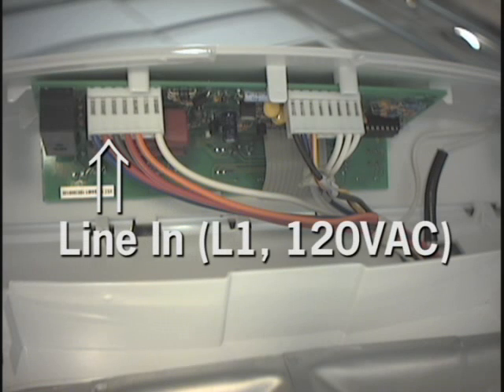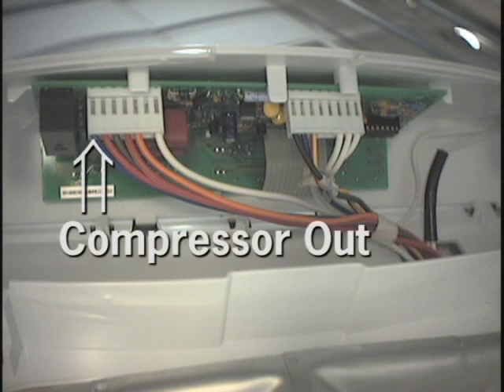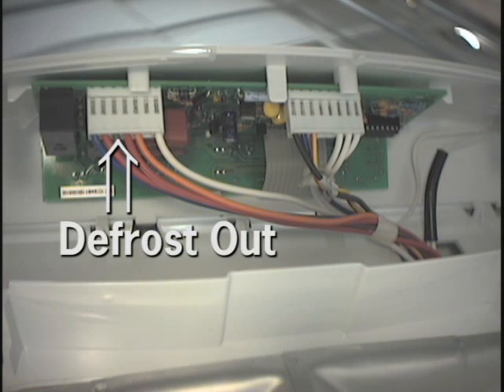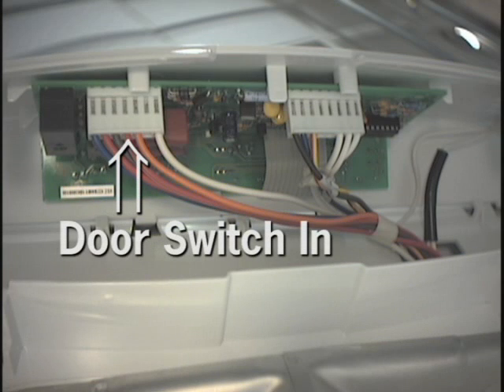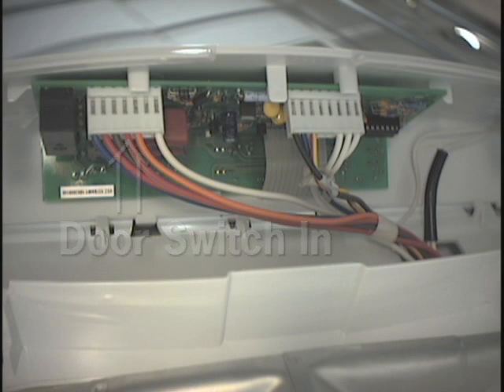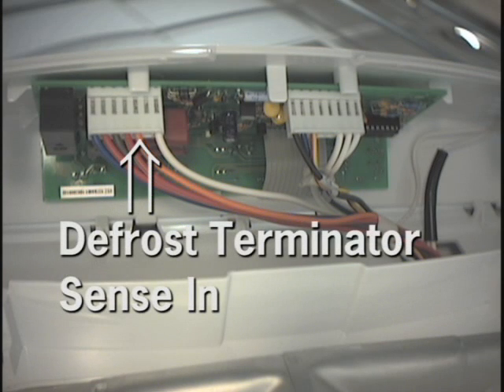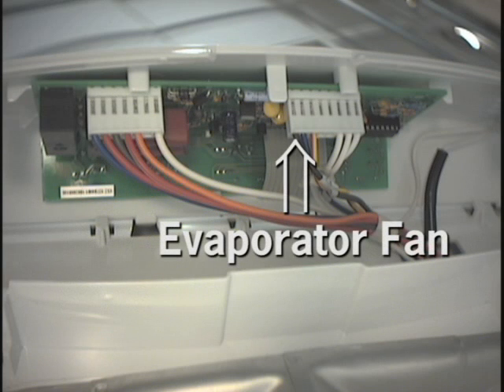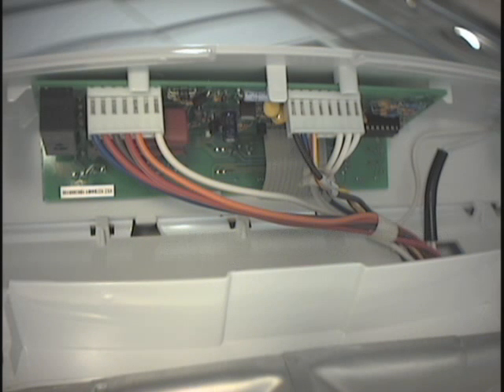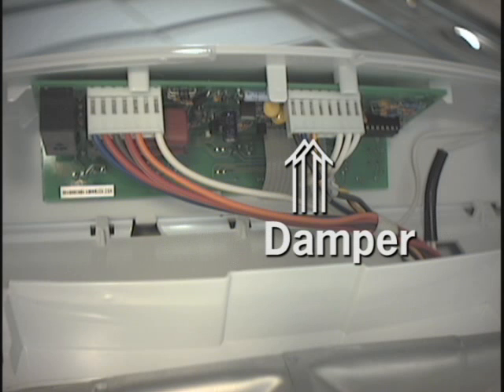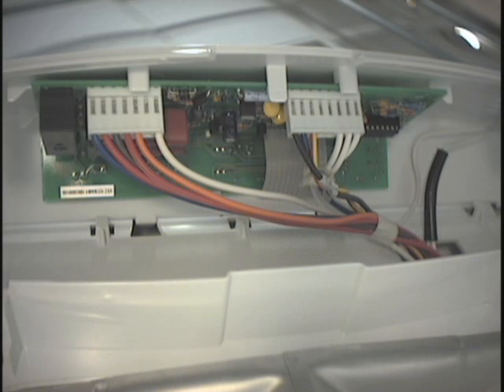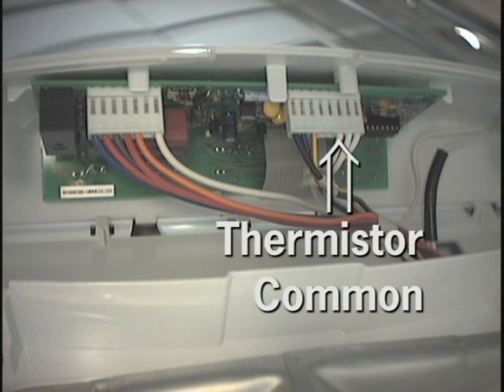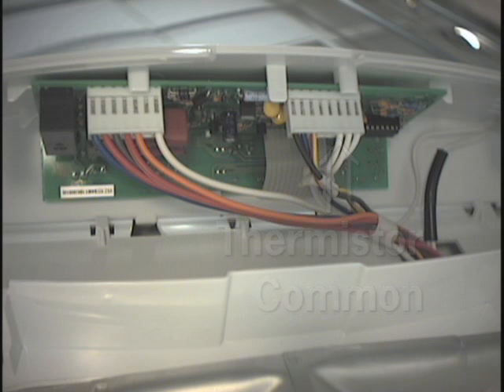Red is power in. Blue is the compressor out. Brown is the defrost output. Red with a white tracer is the door switch input. Orange is the defrost Terminator sense return. The black with red wire controls the evaporator fan. Yellow with red and black with red control the damper. The thermistors are connected between the 3 white wires with tracers.